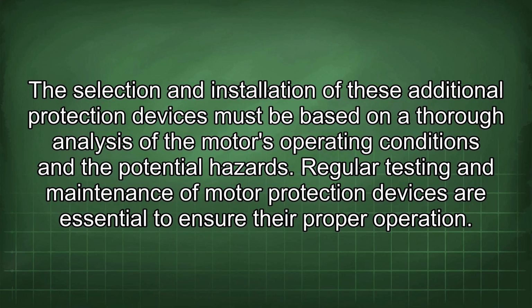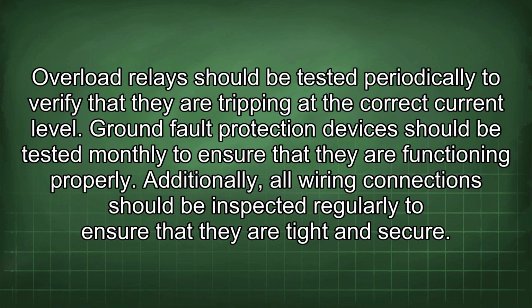Regular testing and maintenance of motor protection devices are essential to ensure their proper operation. Overload relays should be tested periodically to verify that they are tripping at the correct current level. Ground fault protection devices should be tested monthly to ensure that they are functioning properly. Additionally, all wiring connections should be inspected regularly to ensure that they are tight and secure.